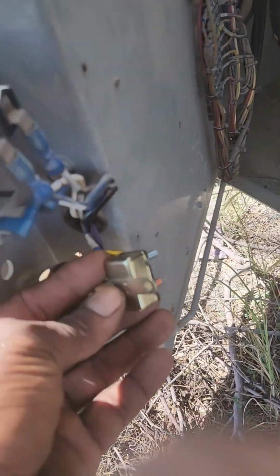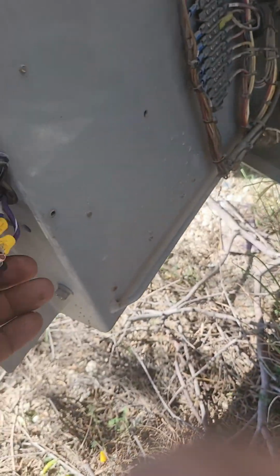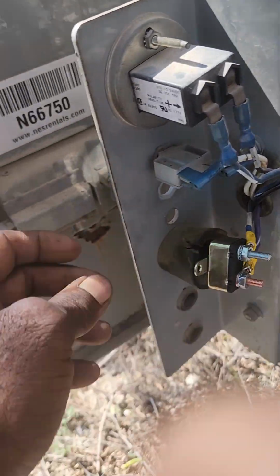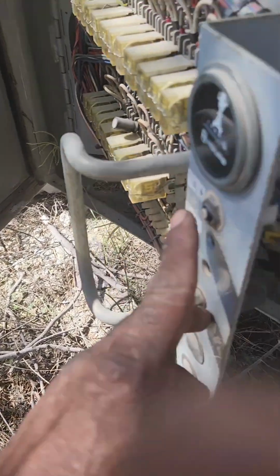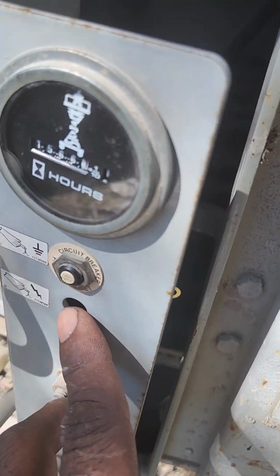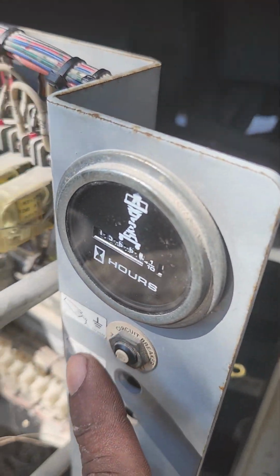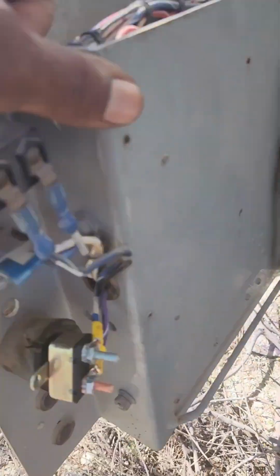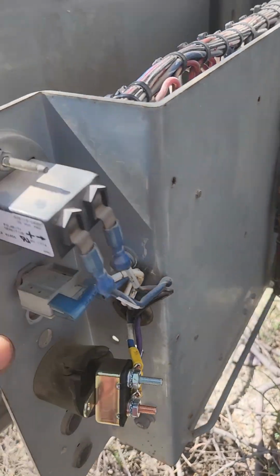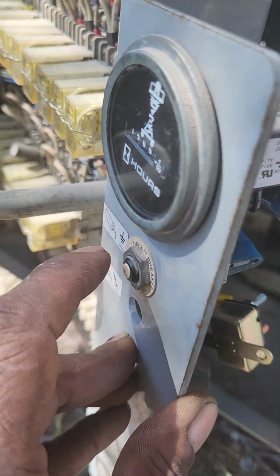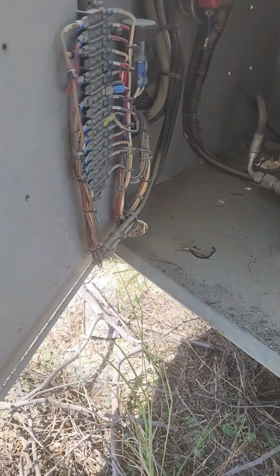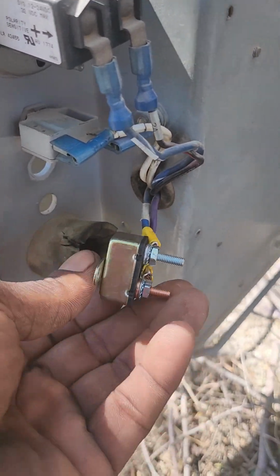I have installed this right here in place of the circuit breaker. There used to be a circuit breaker right here, the same as this one right here. Someone took it out and put in a fuse, and the fuse blew. The problem was that this one here, when you trip it, you push the button and reset it. A fuse won't reset, so I went out and bought this one right here. This is an automatic resetting circuit breaker.